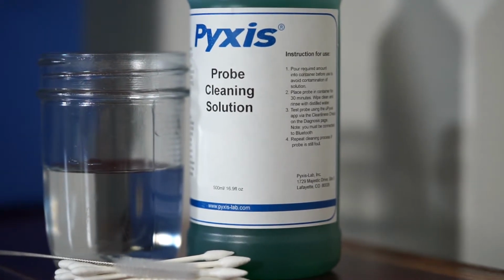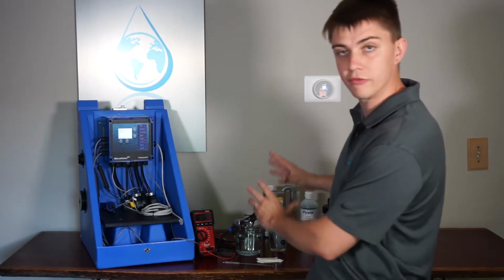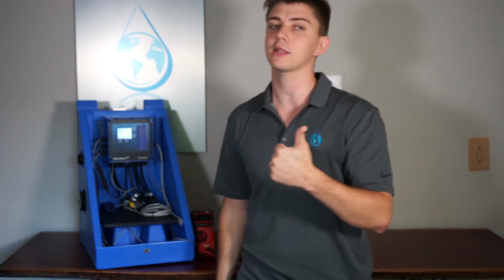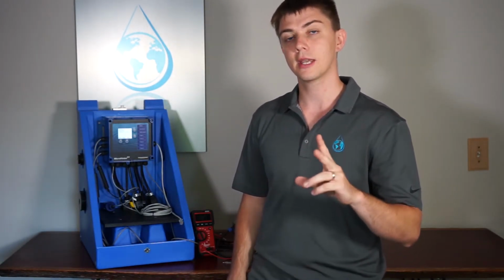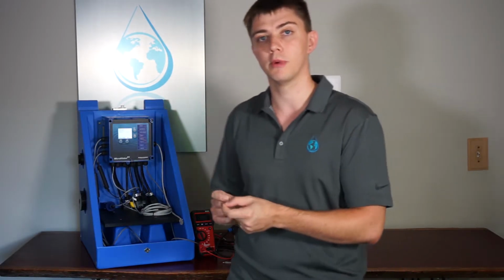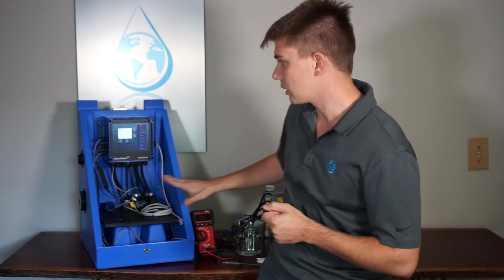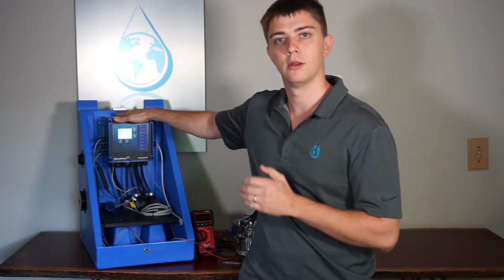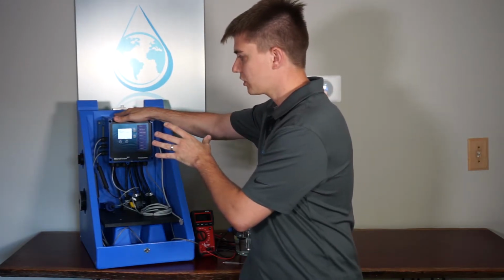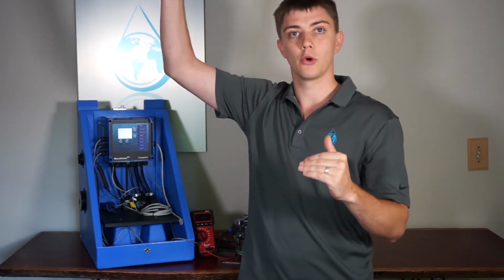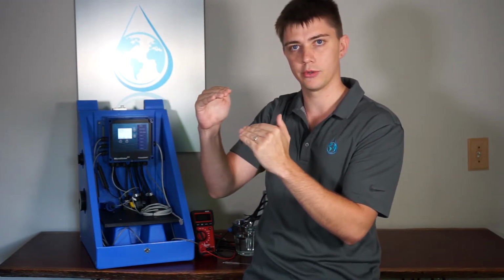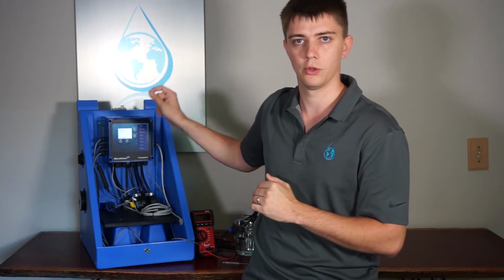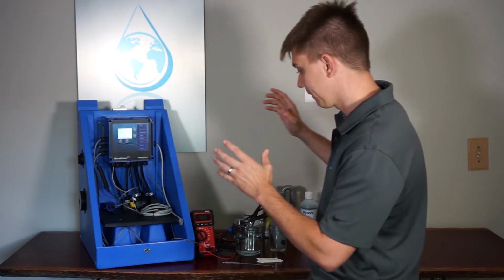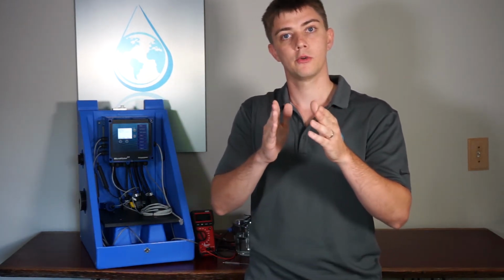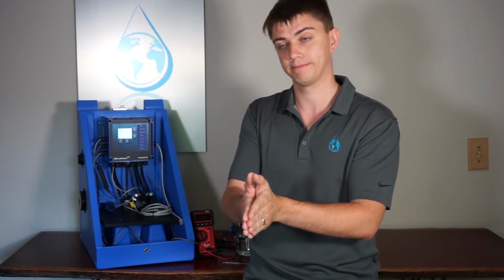You want to make sure you're staying on your control equipment as close to the factory calibration as possible, and that anytime you're drifting, you're addressing it by first inspecting the probe and ensuring it's clean. Second, recalibrate the probe using the probe recalibration tool versus adjusting a 4 to 20 scale on your controller. Adjusting your 4 to 20 scale will typically lead with your range being narrowed, and you don't get as precise control on the controller. So always pull the probe, inspect, clean, and then recalibrate the probe.